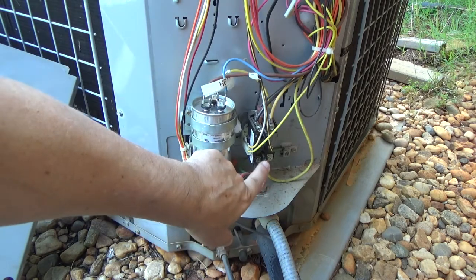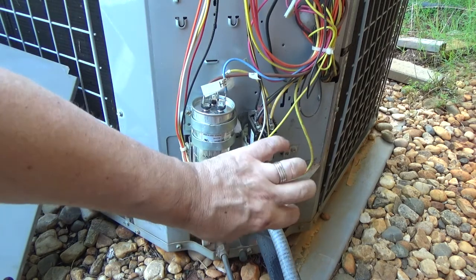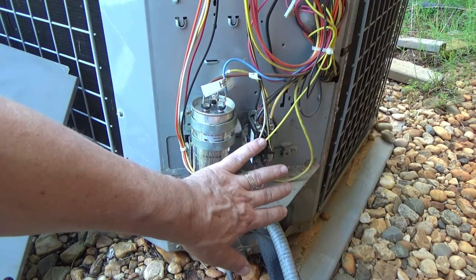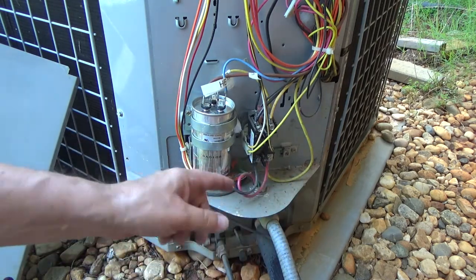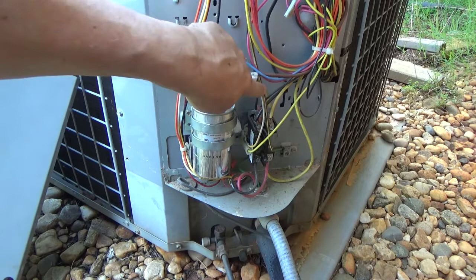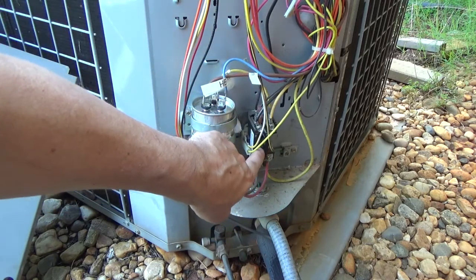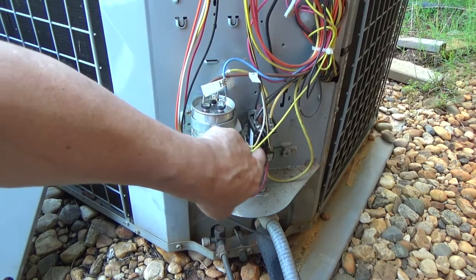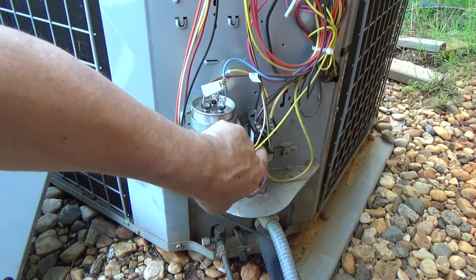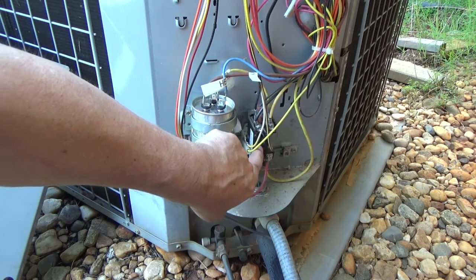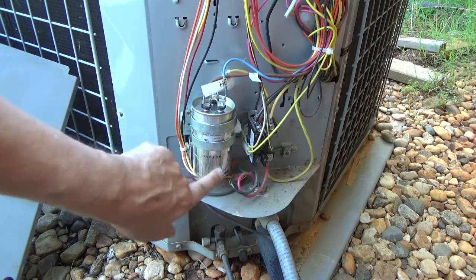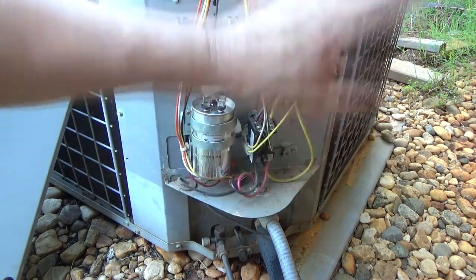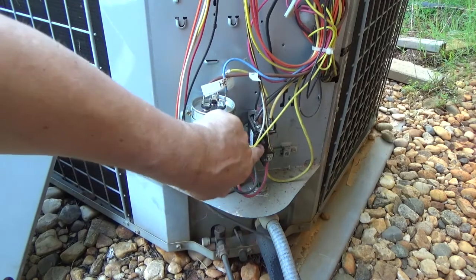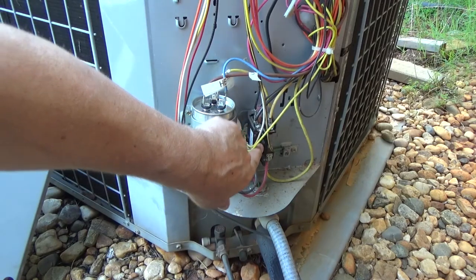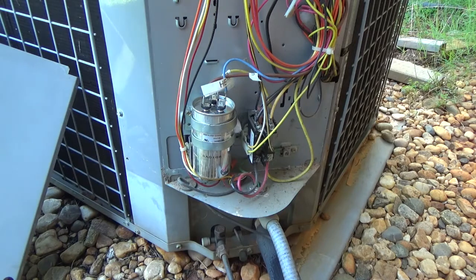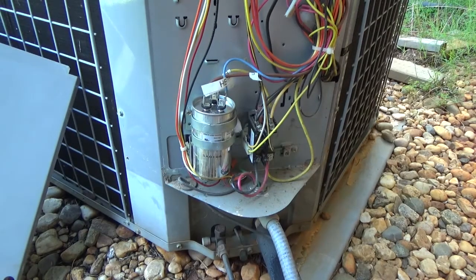Another thing that happens is on the relay, a lot of bugs will get in there. Ants in particular are really bad. They're highly annoying as far as ruining the contact point of your relay. So sometimes if it's not running, you can push that in and it runs. You know your capacitor's bad. So if you have it all hooked up and it's running, and you push in your relay and it all starts up, that's what's going on. But as a homeowner, you're not going to do that, right?